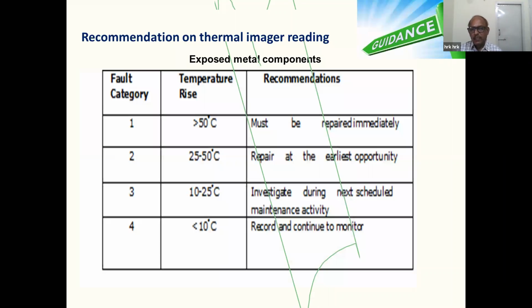Having seen the principle of thermography, how it works and how it is used in various systems in a few cases, when we are using thermography we have to know what to interpret from the image. This is for exposed metal components, like electrical contacts, main panels or distribution panels. Normally, if it is less than 10 degrees, there is no problem, and they can continue without any investigation. If it is between 10 and 25 degrees, we have to go for the next schedule and take the maintenance activity.